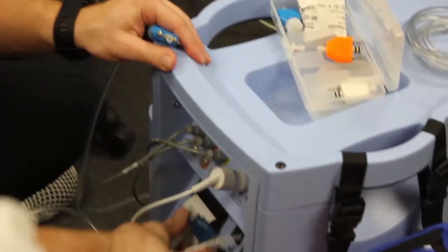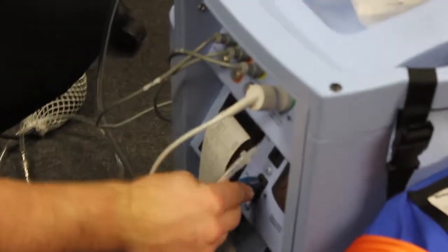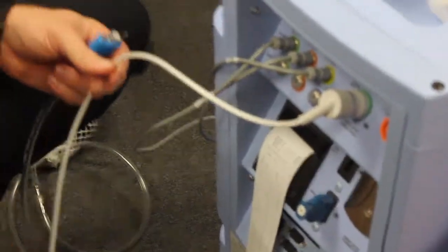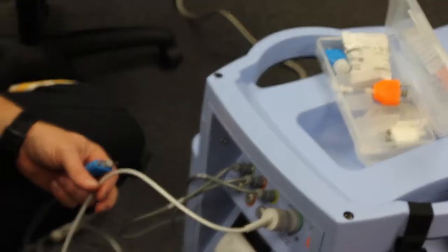and we're going to have the 40cc key already in, either the 40 or the 50, depending on which key you need, already in your balloon pump. You're going to take your Datascope line, or it's most likely going to be a Datascope line if you're having to use a key. If not, you're just going to take it out of the Arrow balloon pump and bring it over. You're going to add it to your key here.